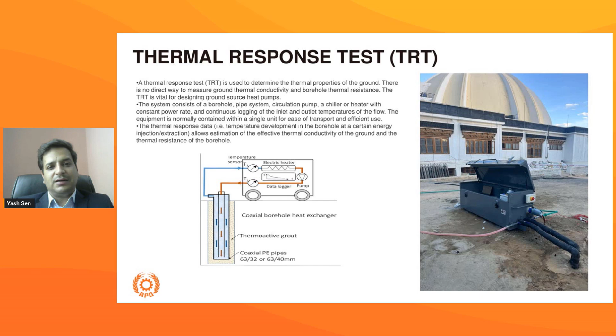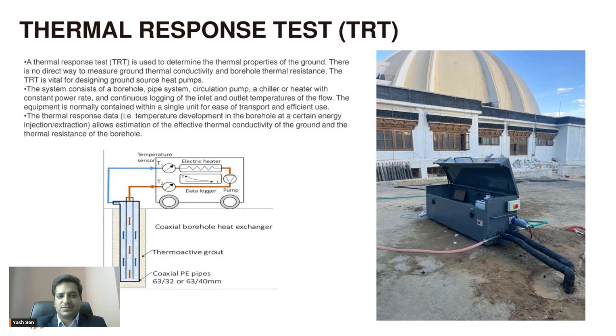All these properties can easily be calculated from the thermal response test. Normally this test runs for 36 to 48 hours, and it's a continuous test in which we run hot water inside the ground loop and check what temperatures we get when the water comes out. We use this sort of machine and do a lot of these tests when doing commercial installations.